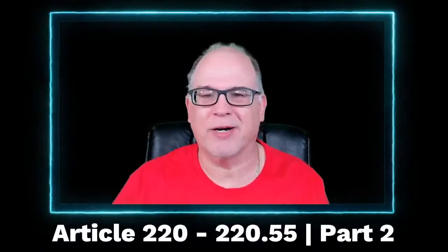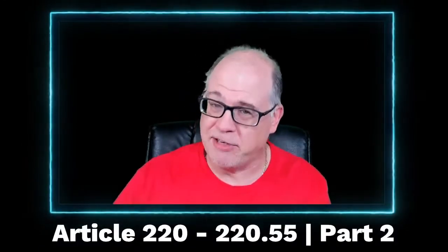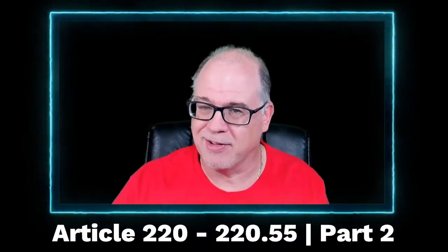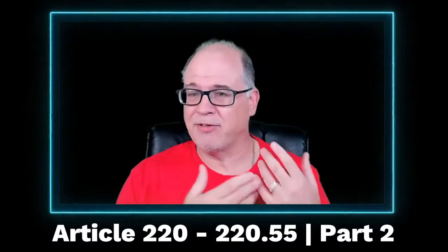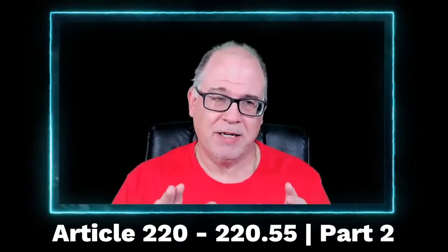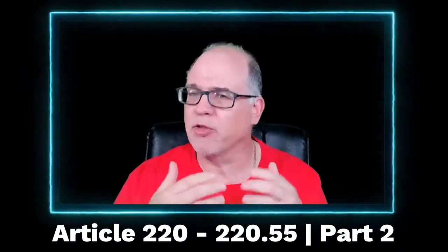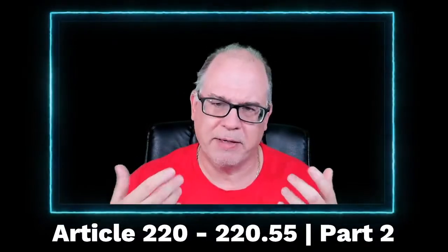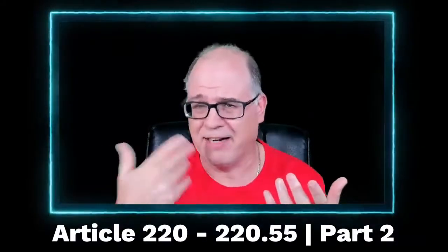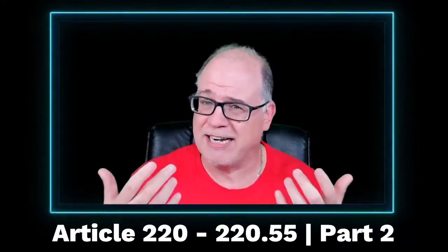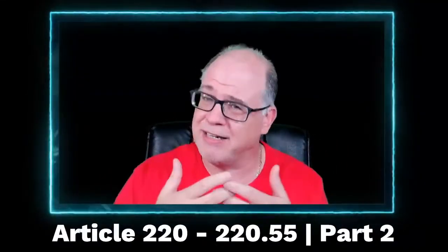In this episode, we're continuing our journey into range calculations, cooktop calculations, and in-wall mounted oven calculations. If you watched part one of this series, it's real important, and if you haven't, go do that, because we cover the branch circuits when you use the nameplate. What happens when you have a cooktop and a wall-mounted oven and you combine them to treat them as a single range? I know it's not a range, but you treat it as a range.